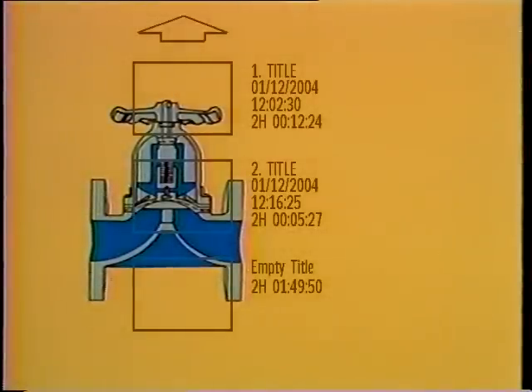There are two basic body designs used for diaphragm valves: the weir and the straight through. The straight through body has no obstructions where the diaphragm seats, and the bore of the valve is the same as that of the piping it's attached to. The weir, on the other hand, has a raised surface where the diaphragm seats on the valve body — this allows for the use of stiffer diaphragm material but reduces the area of flow through the valve. You'll find additional information about materials used in the manufacture of diaphragm valves in your text.